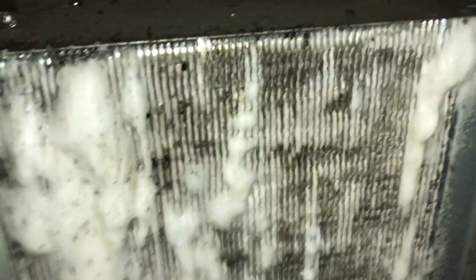All right, got the probe replaced with my temporary probe. Getting this coil cleaned up - it's real dirty, look at that. Get this condenser cleaned up super good, and then we'll run some checks on this thing and see where we're at.